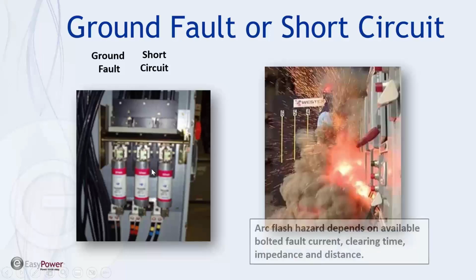So, short circuit and ground fault. Well, let's get into arc flash for a second. The arc flash occurs from a short circuit or a ground fault generally. Very often it's a ground fault that starts it, and then sometimes the air becomes ionized and it takes it to a three-phase fault. So the arc flash itself depends on the available bolted fault current, what that level is. And then the clearing time: how long does it take for the breaker to open or the fuse to blow? That's going to have an impact on how big this arc flash is. As a matter of fact, the arc flash level is directly proportional to clearing time. So the longer it takes to clear, the bigger and badder and the worse the arc flash can become. So that's certainly something to consider.